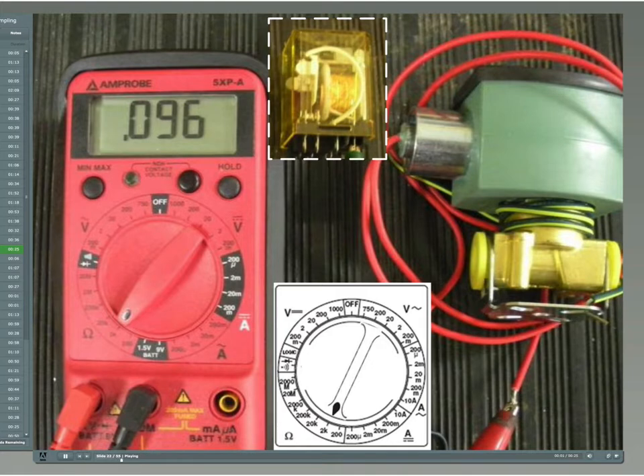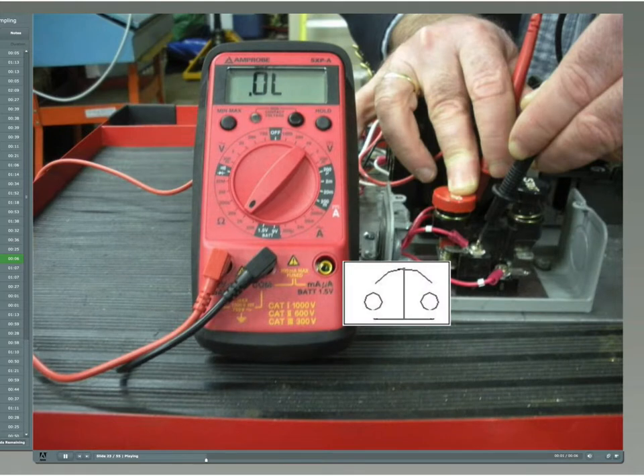The resistance of this valve coil is only 96 ohms and allows for a lot more current flow, about 20 times more than the relay coil we were measuring. Remember the tire with the pinhole versus the nail hole, and the resistance and airflow in CFM. The solenoid coil needs 20 times more current to pull open the valve against the spring that keeps the valve in a normally closed position. NC contacts are actuated, and therefore the ohm meter reads infinite resistance.